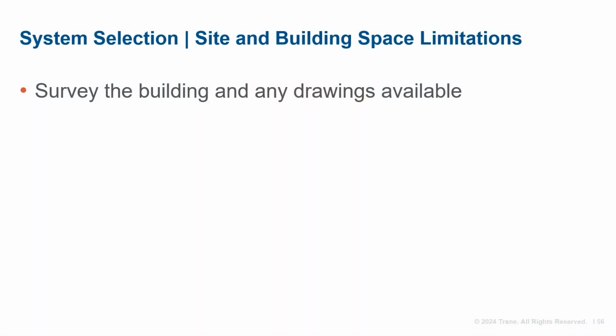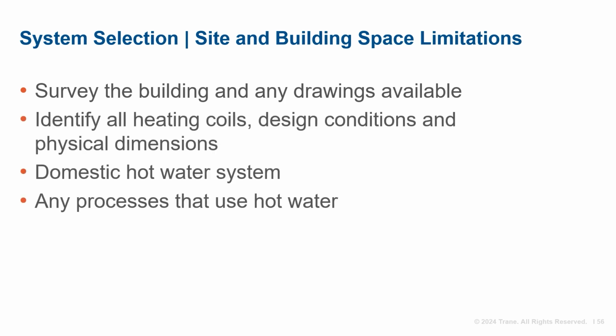Once the project goals are clearly understood and documented amongst all members of the team, the next step is usually survey work. During the building survey, it's critical that all hot water heating, domestic hot water, and steam uses are identified. Coil capacities and physical dimensions, including face area, design airflow, tube rows, and fin spacing, are important for future analysis. Pay particular attention to perimeter baseboard, radiant systems, and any process loads since they're often the most difficult to convert to lower temperatures.